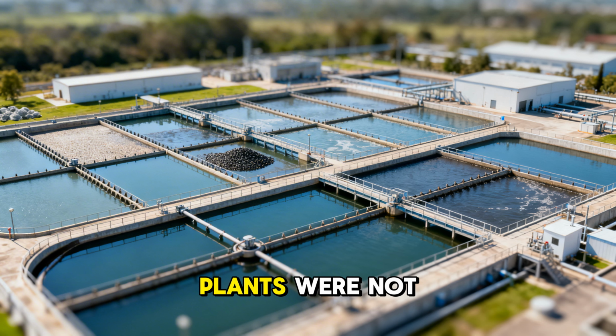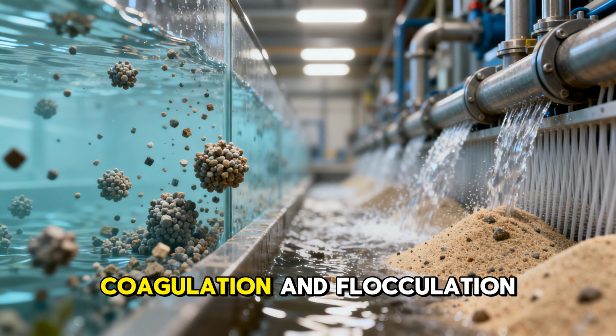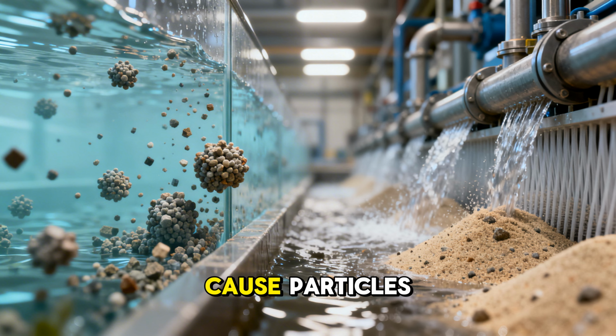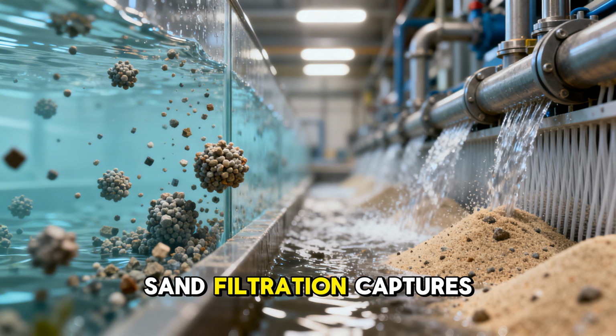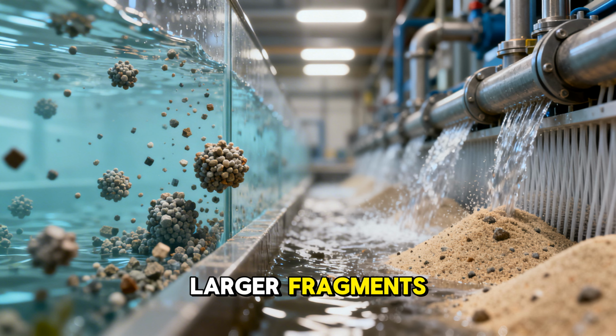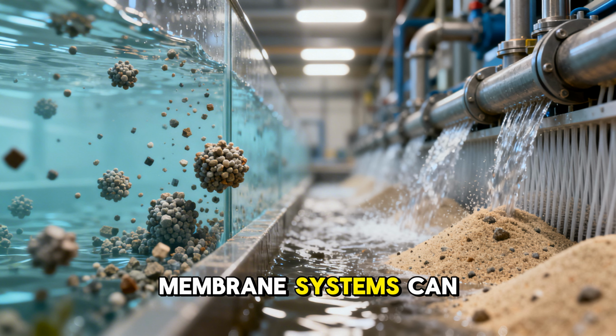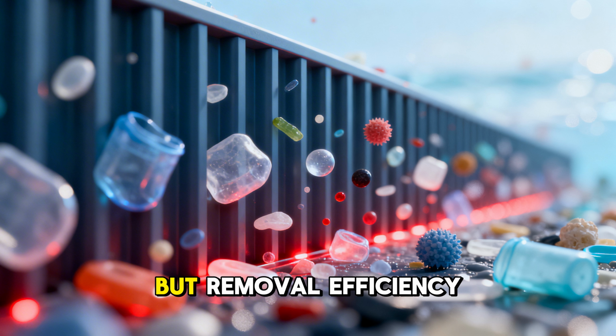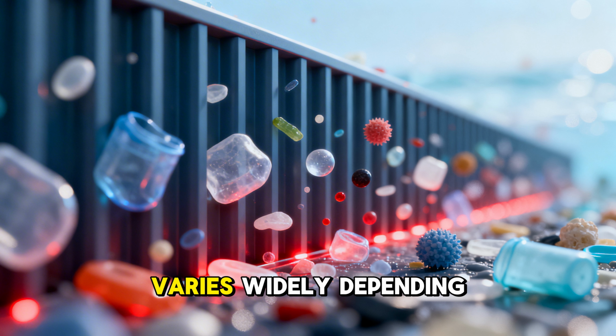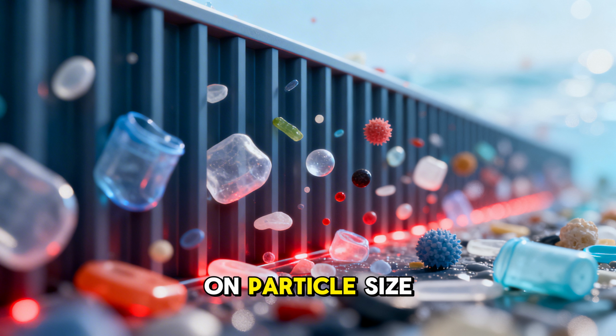Conventional water treatment plants were not originally designed to remove microplastics, yet many of their processes unintentionally act as partial barriers. Coagulation and flocculation cause particles to bind together and settle. Sand filtration captures larger fragments. Membrane systems can remove smaller ones, but removal efficiency varies widely depending on particle size, shape, and density.